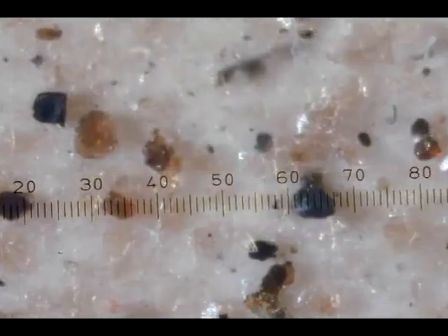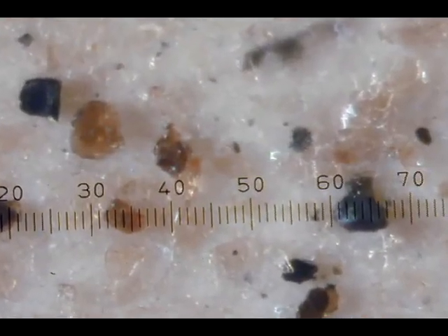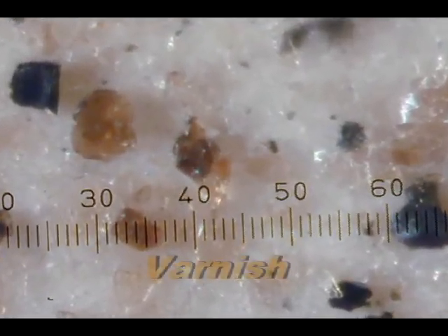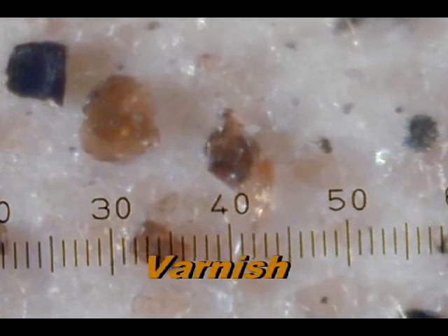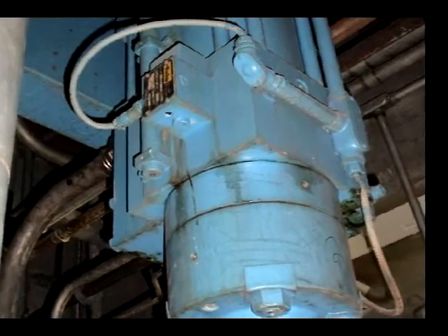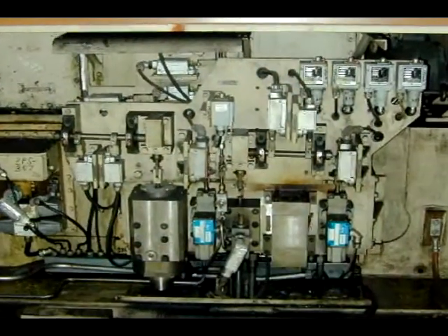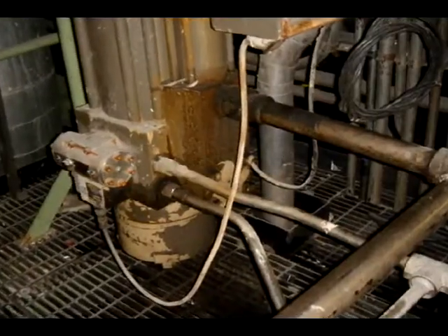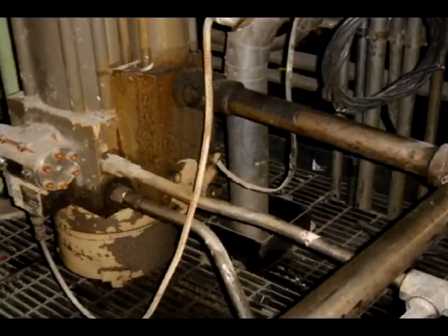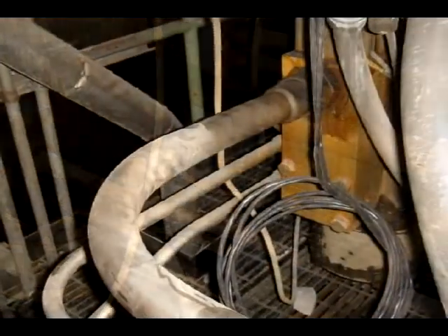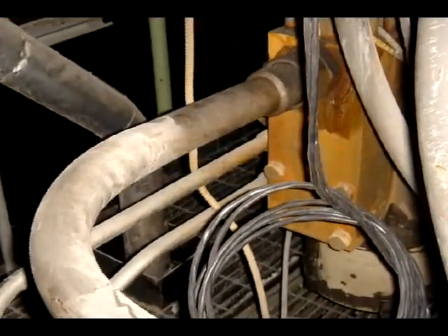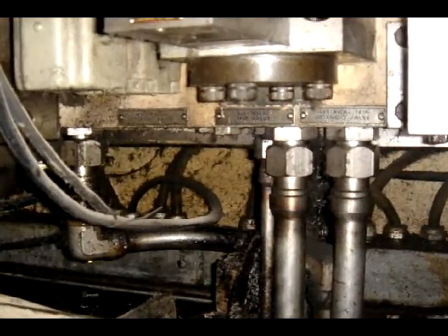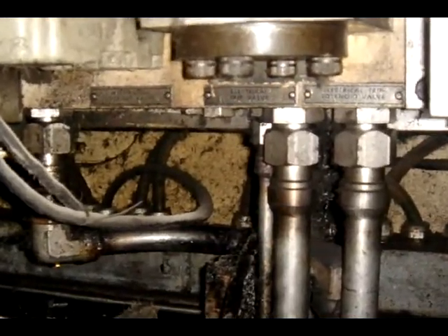Over a period of time, the gels form as hard deposits called varnish on the tubes and pipes of the hydraulic fluid system. The varnish does not generally form on the components of the system since they move and can ultimately scrape off the varnish buildup. On the other hand, the pipes have no moving parts. The fluid flowing through the pipes is under high pressure, but the flow is laminar and there is very little turbulence. This combination allows for easy varnish formation.